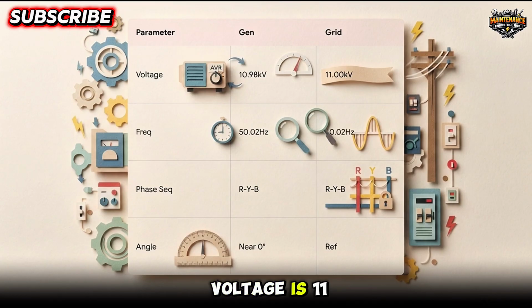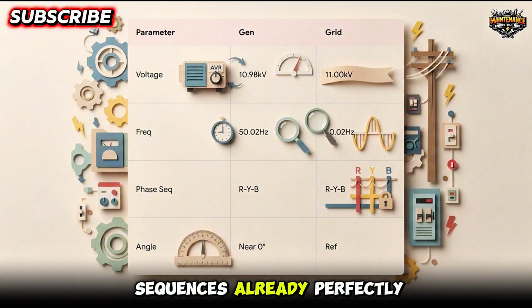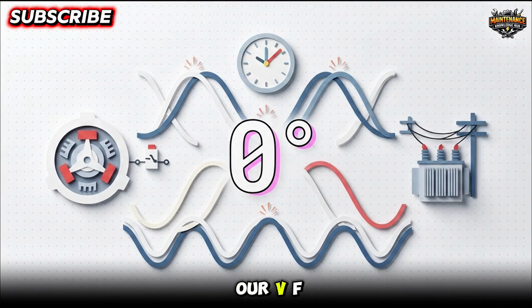And to really wrap your head around how tight these tolerances are, just look at these real-world numbers. Say the grid voltage is 11 kilovolts, and our generator is sitting at 10.98. I mean, that is incredibly close. To perfectly match that voltage, the generator uses its automatic voltage regulator, or AVR for short, which tweaks the excitation system to bump the terminal voltage up or down. Meanwhile, the frequency is off by just a tiny fraction, 0.02 Hz, and the phase sequence is already perfectly matched at RYB. But there's one last P in our VFPP checklist, and that's the phase angle.